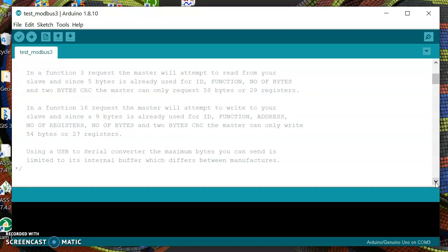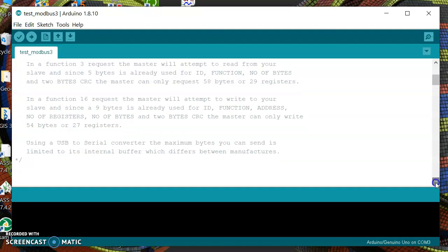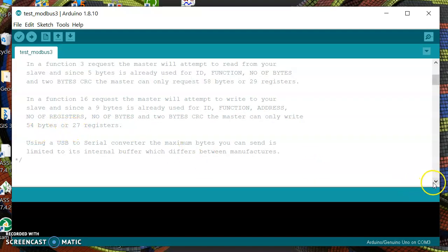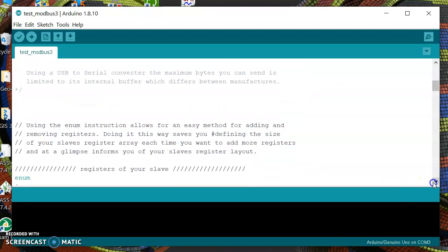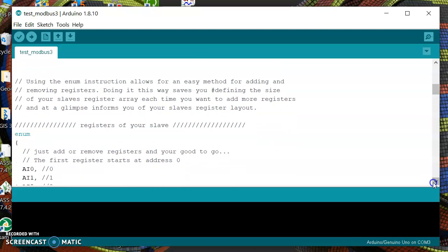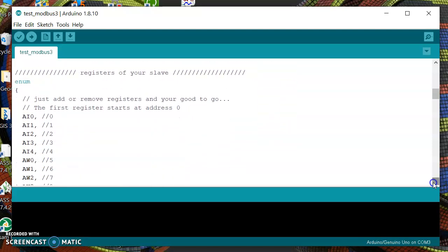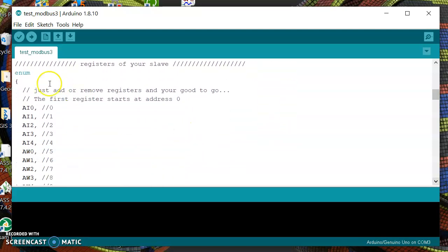In function 16 the master will attempt to write 9 bytes, so you can only write 27 registers in function 16.